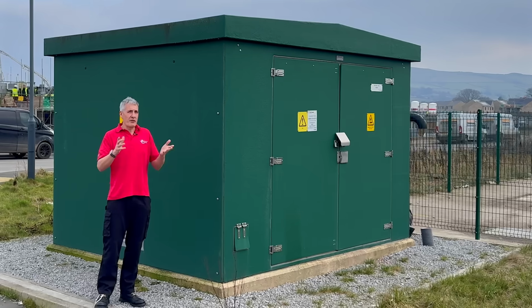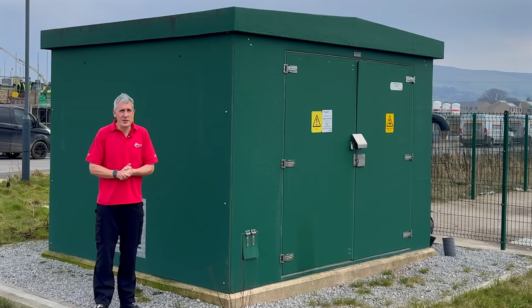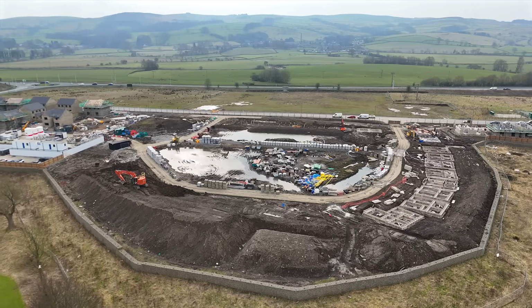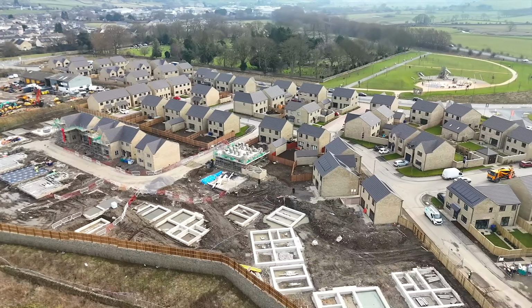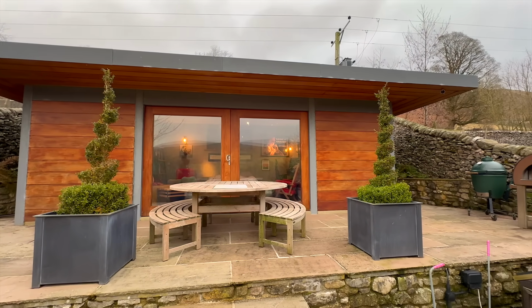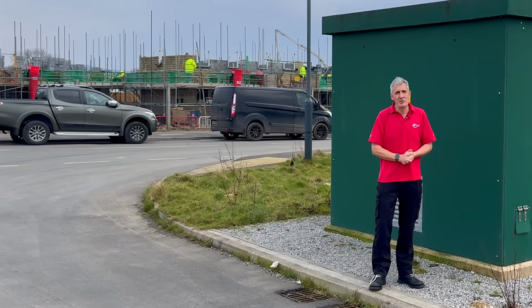Of course, as wiring regulations have developed, there was initially a rush to bring in surge protection, often based on a risk assessment as to how close you are to the substation. But look at the market now, with all houses, especially new builds, being fitted with surge protection. That reduces the risk for everybody. But also, don't forget about remote buildings in an existing installation. If they're any distance from the consumer unit, they may need additional surge protection too.